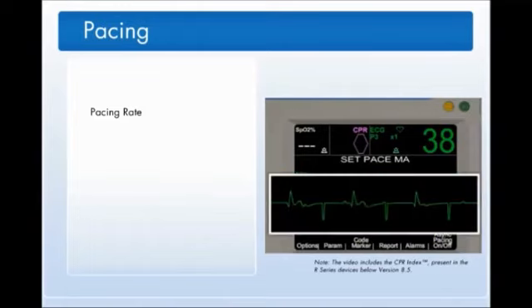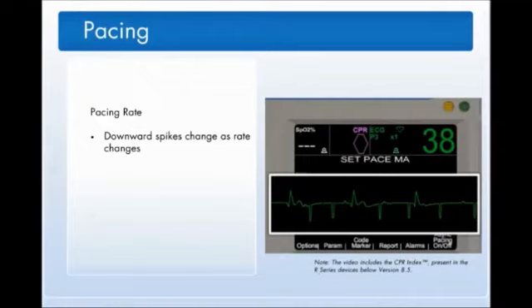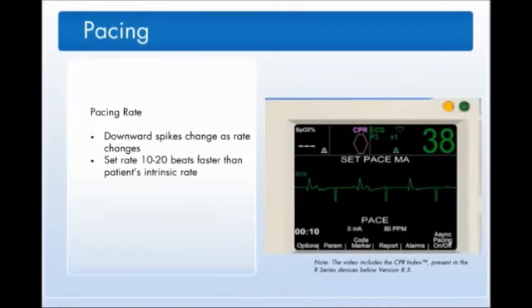Observe the downward pacing spikes on the monitor. As you increase the rate, the downward spikes get closer together. As you decrease the rate, they move further apart. Set the pacer rate to be 10 to 20 beats faster than the patient's intrinsic rate and high enough to generate a sufficient cardiac output.